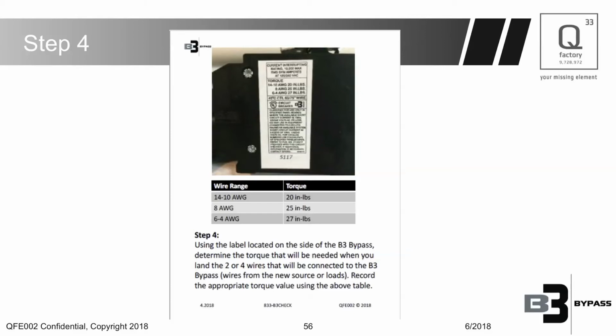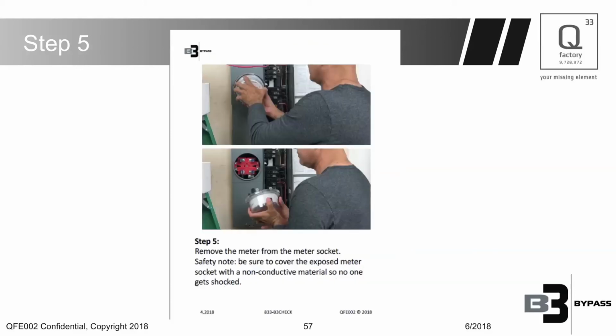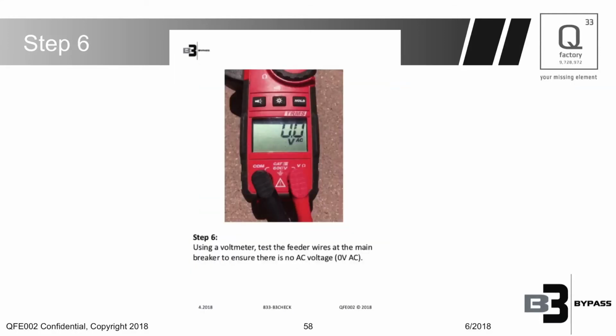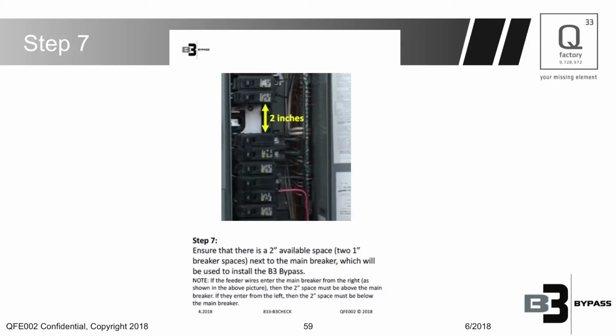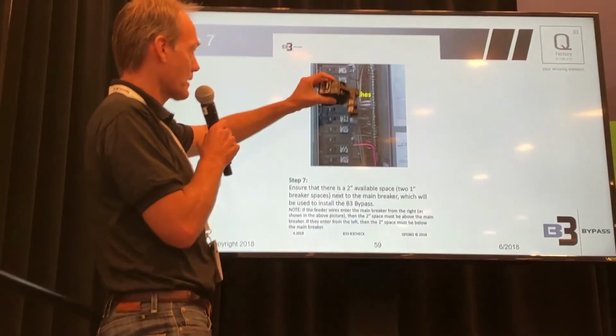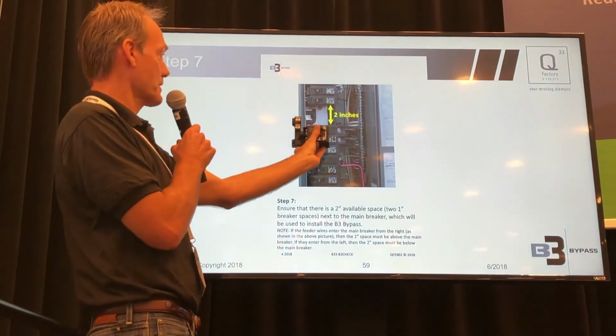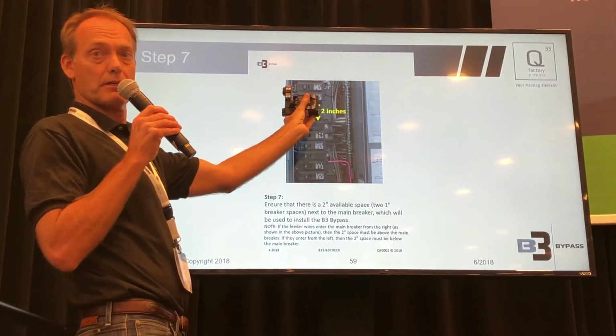Okay. And then next step to the installation process, pull the meter. Again, follow utility guidelines to do this. We want to make sure everybody's safe. Once you pull the meter, please do a measurement. We want to make sure that you're safe, everything's de-energized. Okay. Additionally, when the meter's pulled, if you're going to have people around, please use a non-conductive material to cover the meter socket. Just some typical best practices. All right, so we're going to need 2 inches of space to install this. If the feeder wires are coming in from the right, the 2 inches of space need to be above the main breaker. If the feeder wires are coming in from the left, the 2 inches need to be below the main breaker. Okay?